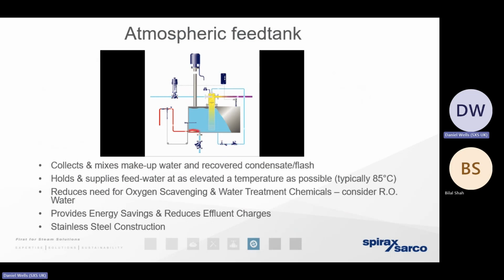So one of the most important components in the boiler house is what we call the hot well, the feed tank. This is where we want to contain all of that hot water that we're bringing back from the various points around site to the energy centre, and we hold it in storage. Typically, the capacity of the hot well is 1 hour's steaming capacity. So if our client is producing 20 tonnes of steam per hour, that hot well will need to hold 20 tonnes of water. And we want to keep that water at the highest possible temperature.